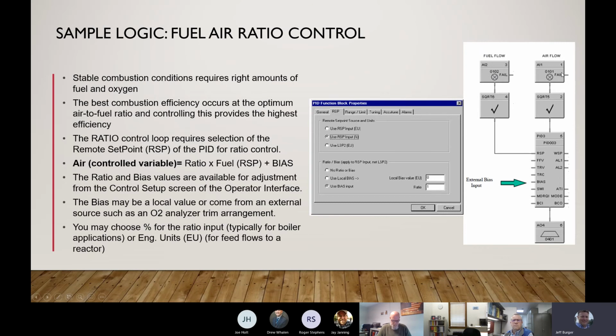And then you have your airflow coming in on another analog input, both of these feeding into a PID loop block and then sending an analog output signal. This is pretty typical for a fuel-air ratio system, and as you can see, if I double click on this PID block, again, I have tabs along the top that allow me to go in and configure that PID block to serve my application needs.